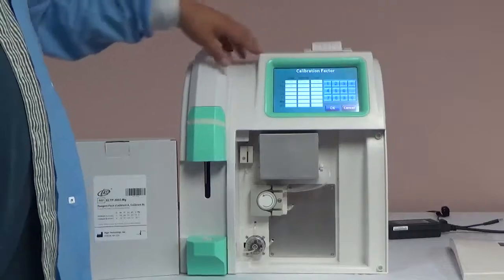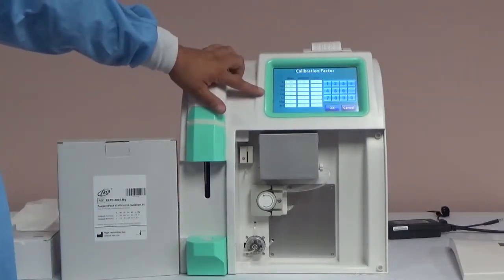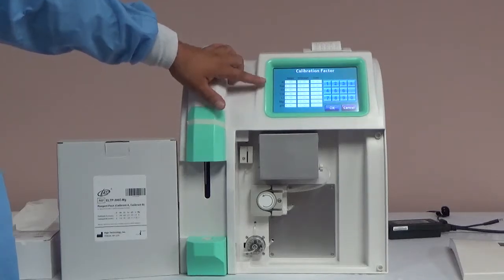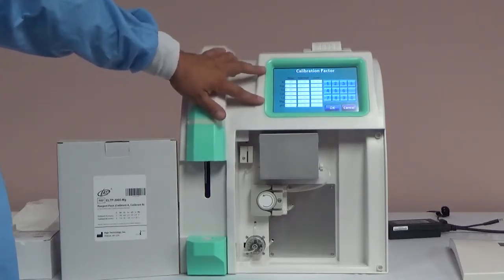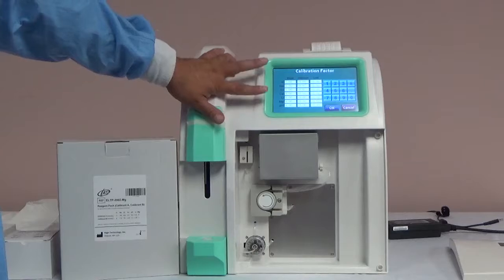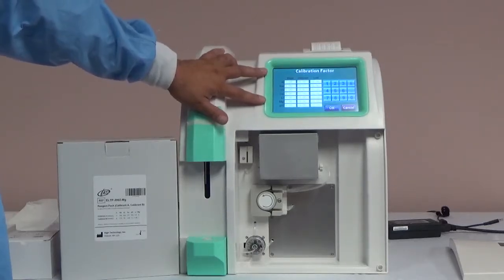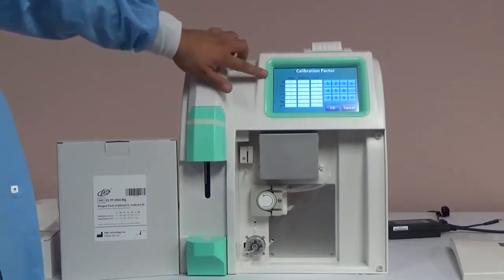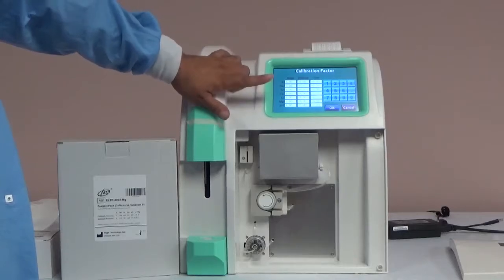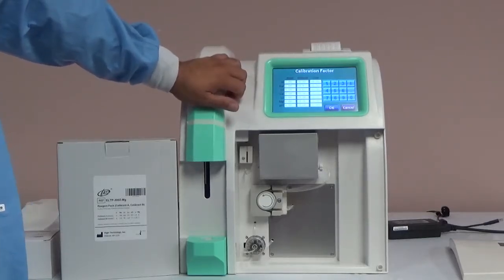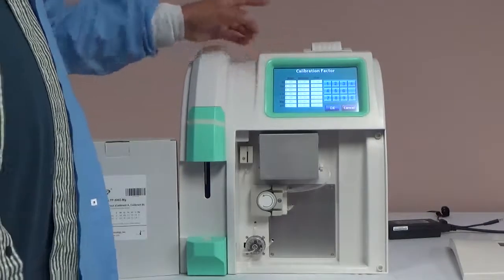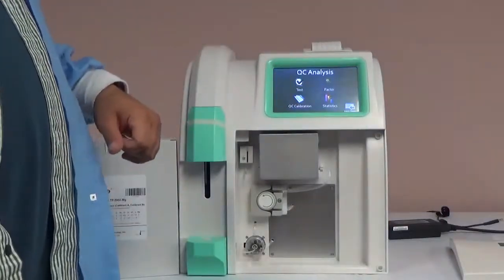Quality control can be accessed from the main menu and then QC. For international customers, verify that the factors are already entered by selecting Factor on the QC analysis screen. For customers that do not already have factors programmed into their analyzer, a QC calibration will need to be run. For international customers, the QC calibration will be run anytime you notice a drift in your results, even if only one parameter is off.